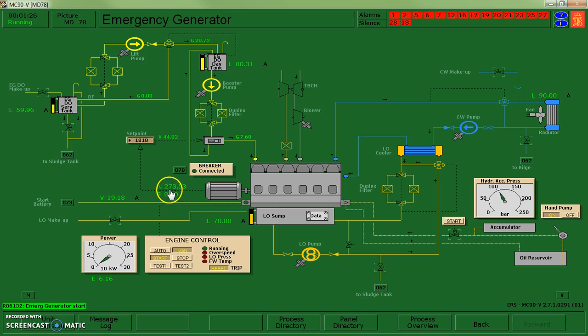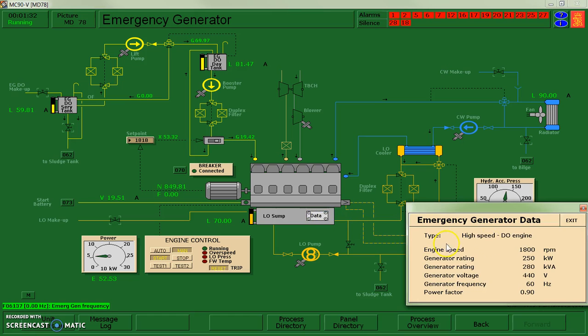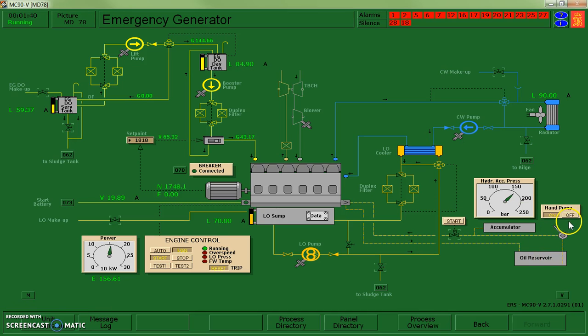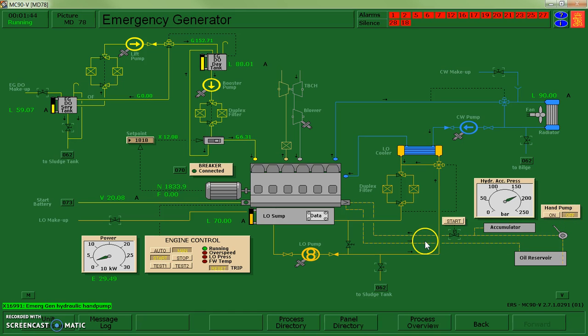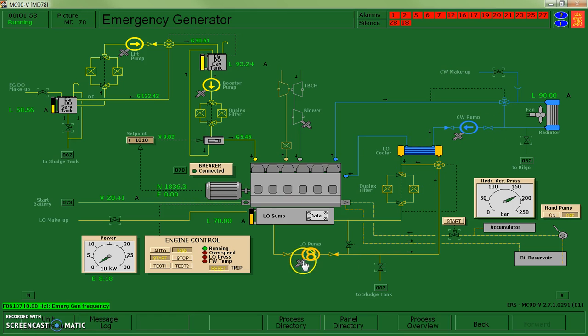My speed is increasing. It has a set point of about 1800 RPM. So I'm looking for my speed to get up into that range. I'm going to turn off my hand pump. It's ready to restart at some point. And you can see I've stabilized around 1800. I've got some cooling water and lube oil, and I appear to be running OK.